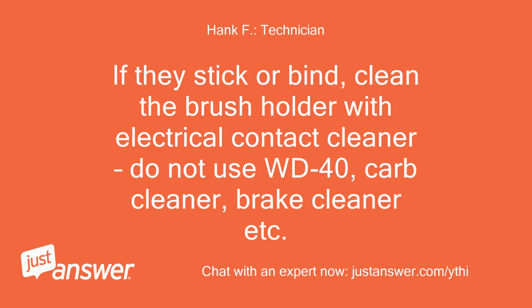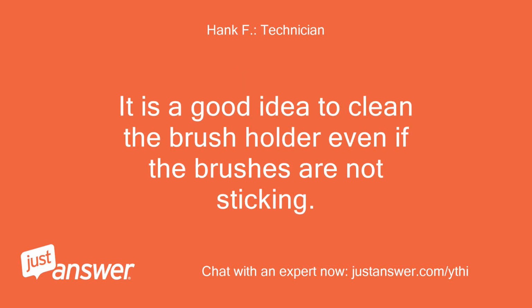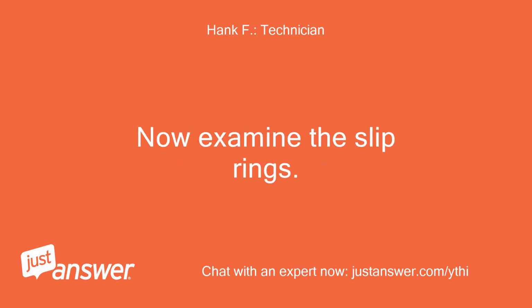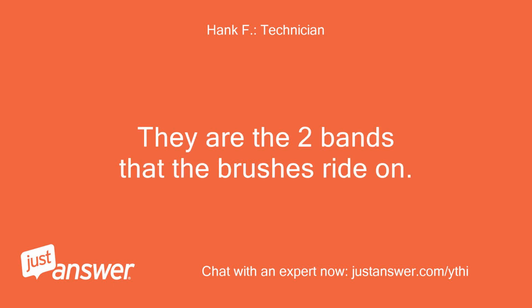If they stick or bind, clean the brush holder with electrical contact cleaner. Do not use WD-40, carb cleaner, brake cleaner, etc. It is a good idea to clean the brush holder even if the brushes are not sticking. Now examine the slip rings. They are the two bands that the brushes ride on.